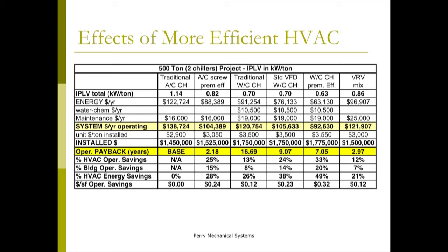And then also at the end here, I've shown the VRV system. On a large system, it just keeps that same kind of payback because it's a modular style system. Now the drawback, especially on a larger building like this, is that a VRV system is like dealing with a bunch of little split systems as far as the maintenance goes. So you're going to have a lot more filters to deal with, a lot more individual components to deal with. So for a lot of institutional customers, they don't have the staff to deal with those multiple pieces, and they like the centralized systems, which is why a lot of times we push towards a chilled water system in our environment. But on smaller buildings, the VRV type system is definitely something that should be evaluated.